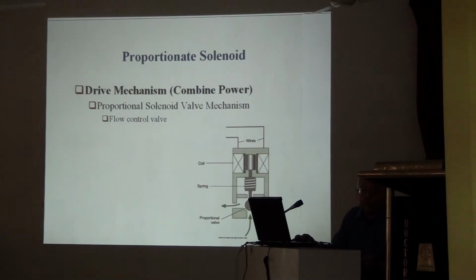Up till now, what you have seen, piston and all these things, spring loaded drive, concertina bag, all these are on the basis of generation. But this drive mechanism is completely dependent on some other pneumatic source. Some compressed air has to be delivered to this valve from the compressor or from the cylinder. It goes into this type of valve.